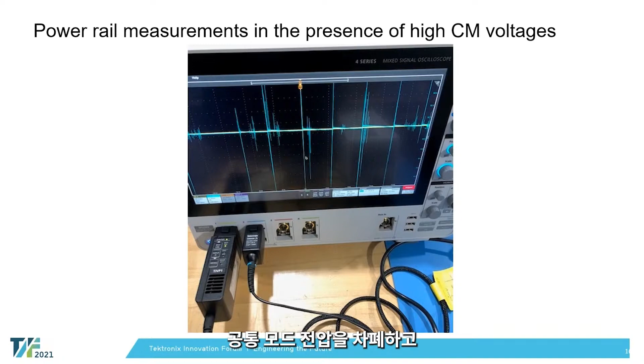Another potential application is using IsoVu with high-speed serial applications, again in the presence of high common mode. Low voltages, in the 1 to 2 to 5 volt range, are really well suited for IsoVu. You can see one example with a 40 megahertz clock measured with two different probes: the top traces from our TIVP, and the bottom traces from a traditional 1.5 gigahertz differential probe. In a high common mode environment, there's a lot more ringing or noise visible on the tops and bottoms of the traces. So if you're looking to validate where ringing is coming from, IsoVu can help confirm whether it's from a common mode source or not.